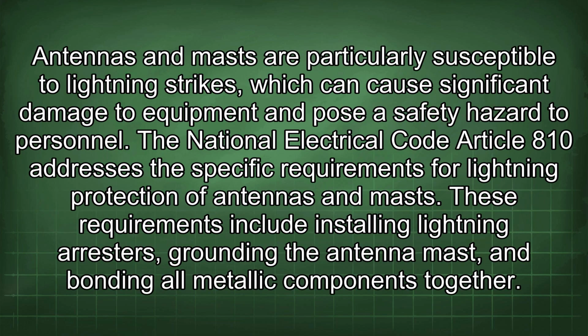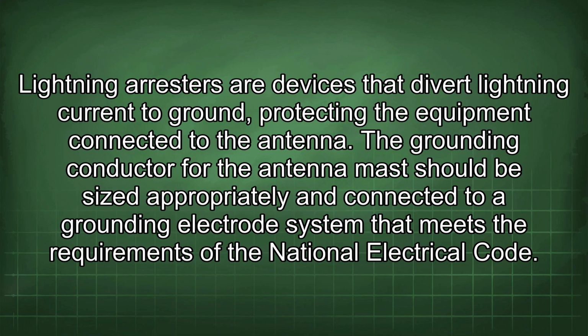Antennas and masts are particularly susceptible to lightning strikes, which can cause significant damage to equipment and pose a safety hazard to personnel. The National Electrical Code Article 810 addresses the specific requirements for lightning protection of antennas and masts. These requirements include installing lightning arresters, grounding the antenna mast, and bonding all metallic components together. Lightning arresters are devices that divert lightning current to ground, protecting the equipment connected to the antenna.